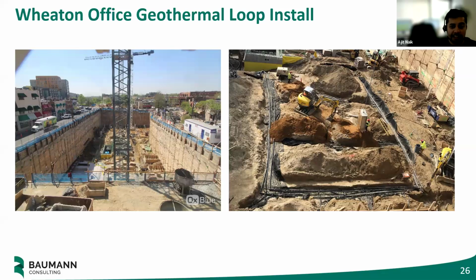So there's a Canadian technique, pretty common now in Canada and starting to become more common here, which we used here: you drill from grade. If you know your foundation is going down 80 feet and you need 400 foot boreholes, you just start at grade while you're doing permits and other stuff. You dig a hole 480 feet deep, drop the tube, cut it and cap it at depth, seal off the tube, and then continue your excavation for your foundation. As you dig out and develop your foundation, you eventually arrive at the tubes you already bored, cut, capped, and sealed, and can proceed with construction. This is a pretty clever way of doing boreholes underneath a building while minimizing the impact to your schedule - super beneficial.